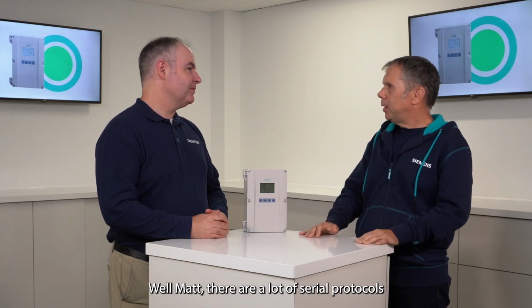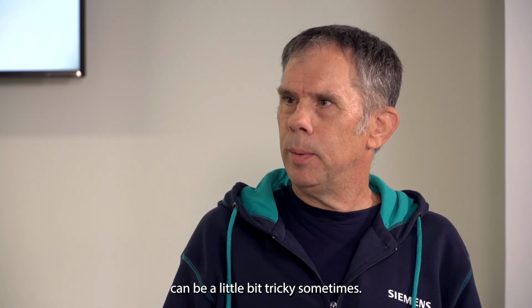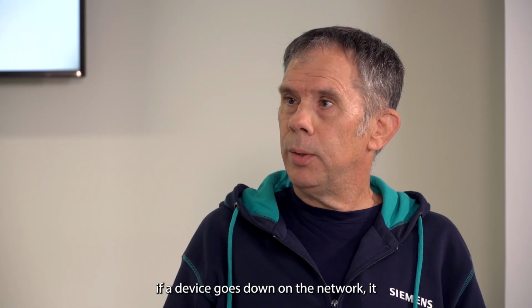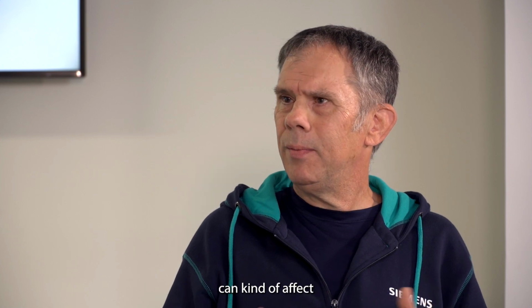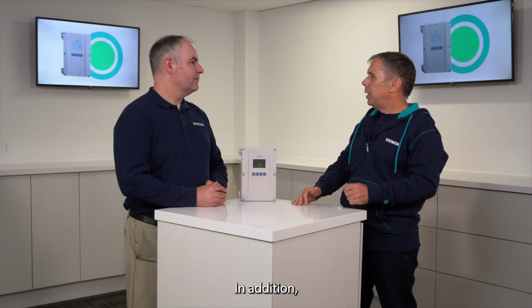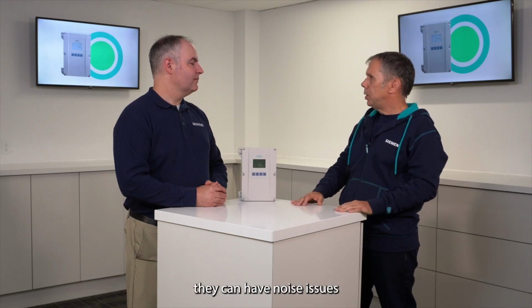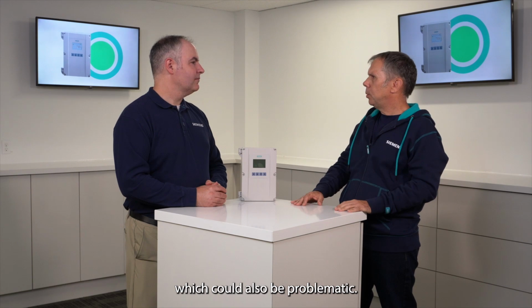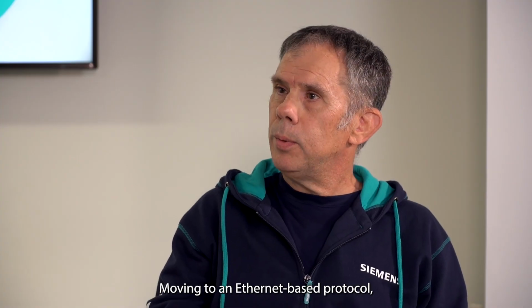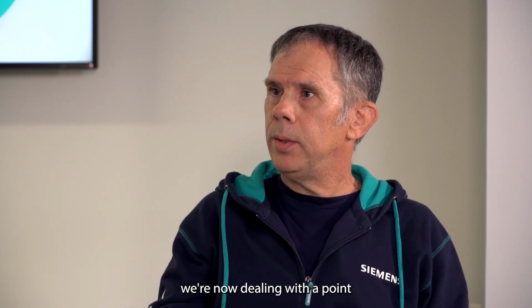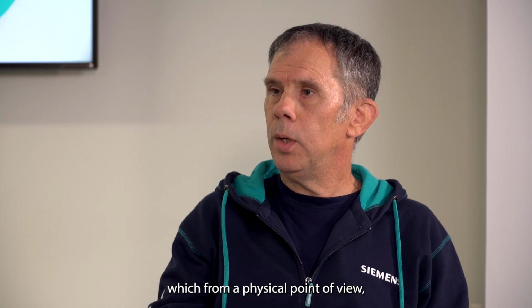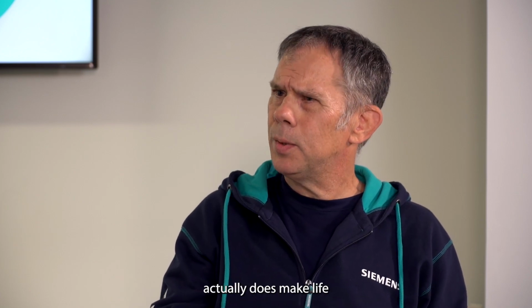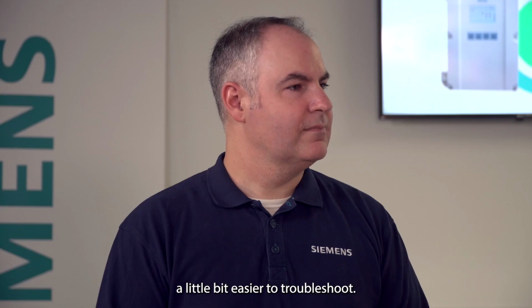Well, Matt, there are a lot of serial protocols out there which work very, very well. However, troubleshooting can be a little bit tricky sometimes. So, if a device goes down on the network, it can affect other devices on that network. In addition, you can have noise issues or grounding issues, which can also be problematic. Moving to an Ethernet-based protocol, we're now dealing with a point-to-point connection, which, from a physical point of view, actually does make life a little bit easier to troubleshoot.